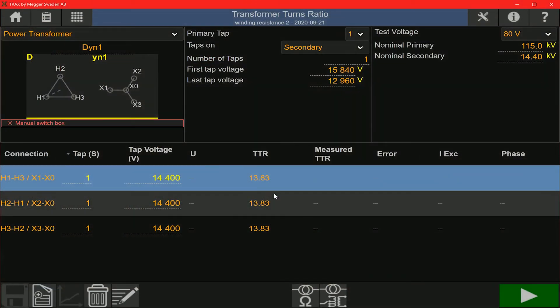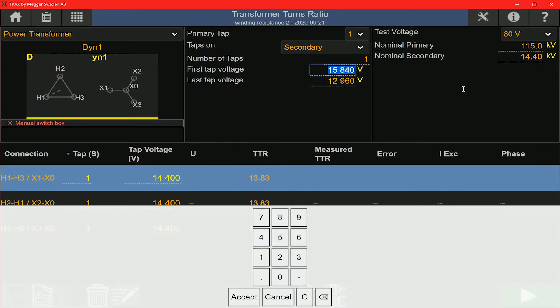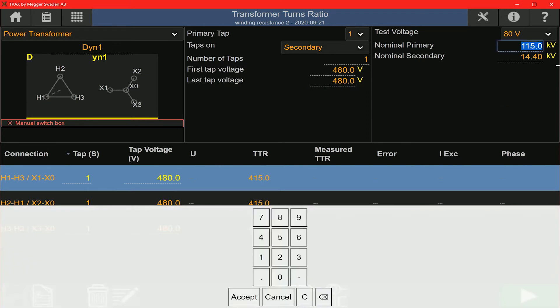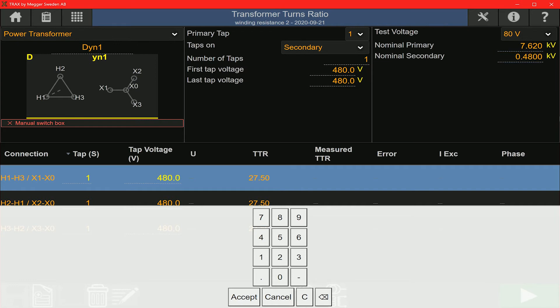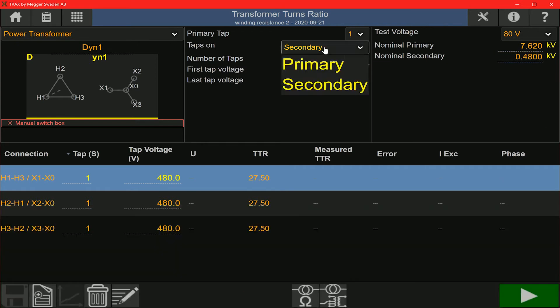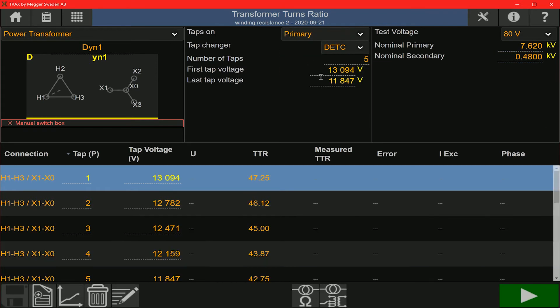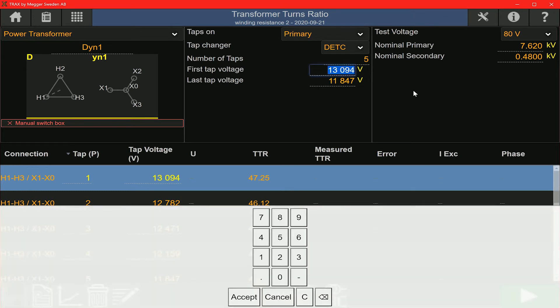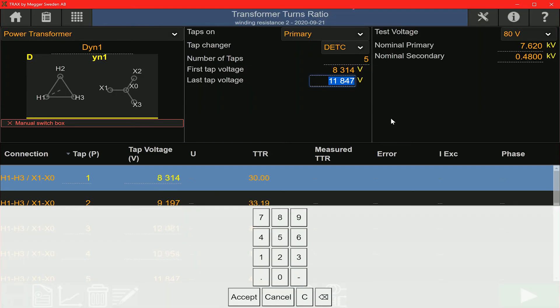In the turns ratio app, you're going to start by entering some relevant information there. You can see that the vector group is already selected as Dyn1. I'm going to change the tap information for the secondary winding here. There are no taps on the secondary winding, so the number of taps is set to 1. The extreme tap voltages would be the same and equal to the nominal voltage. I'm going to change the nominal values for the primary and secondary winding on the right there. In the middle section, I'm going to switch to primary winding and I'm going to change the extreme tap voltages for the primary winding. The primary winding has a DETC type tap changer and it has five taps on it. When I change these extreme tap voltages, you will see in the test section below that the intermediate tap voltages are going to change.